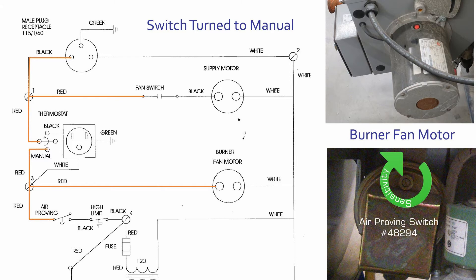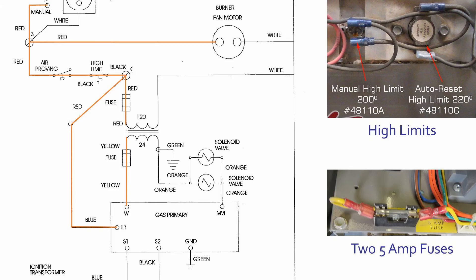The air proving switch is then energized to make sure the burner motor is supplying enough airflow. Next, the high limit switch is activated. If the airflow temperature is below the maximum temperature value, the high limit switch is then satisfied.